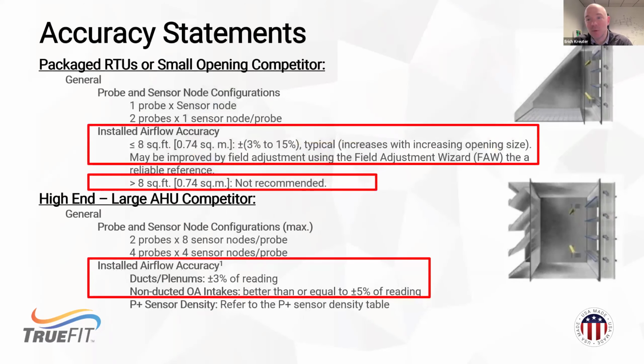And if we dig a little deeper, we'll find that these types of sensors installed in these locations, typically, even from the manufacturers, it's no fault of their own or no fault of technology. We're putting it in a place that's not necessarily ideal. So the accuracies are going to get wider. The repeatability is going to get wider as well. And it certainly leaves a little bit more to be desired.